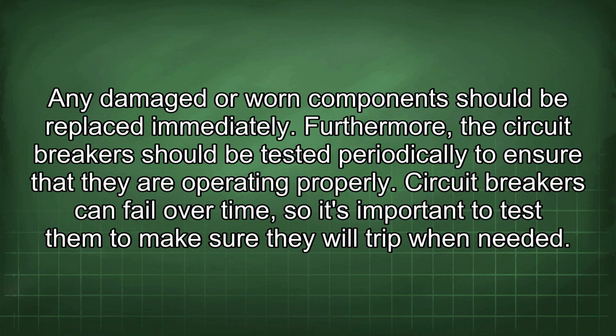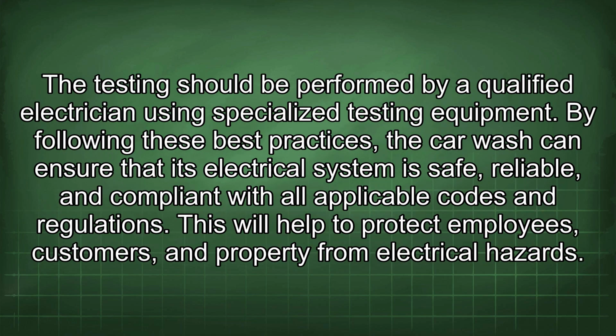Furthermore, the circuit breakers should be tested periodically to ensure that they are operating properly. Circuit breakers can fail over time, so it's important to test them to make sure they will trip when needed. The testing should be performed by a qualified electrician using specialized testing equipment.